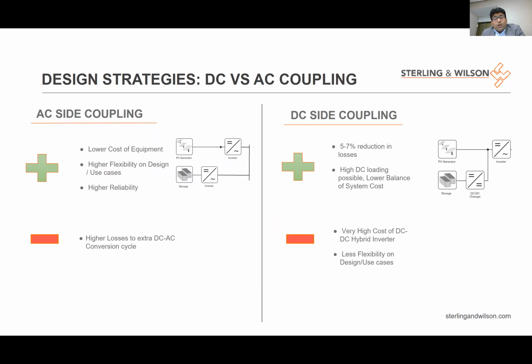When we talk about design strategies, there are a couple of configurations we can follow. We can follow a very typical configuration which everybody seems to be doing nowadays, which is coupling the solar power plant and the storage system on the AC side - meaning you have a normal solar power plant evacuating at 33 or 132 kV level, and an energy system with a hybrid inverter, again evacuating at 33 or 132 kV.